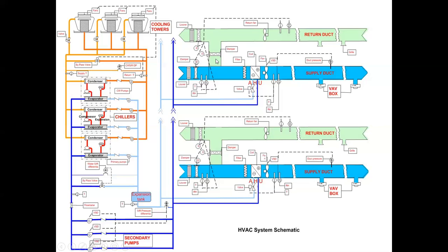If you have a centrifugal chiller, it has a coefficient of performance. You remember what a COP is from your thermal class? Okay, so let's say I needed a million BTUs per hour of cooling. If the COP is 6, I divide that by 6, and that's the number of units of electricity I have to put in, because I get 6 to 1 on a COP.